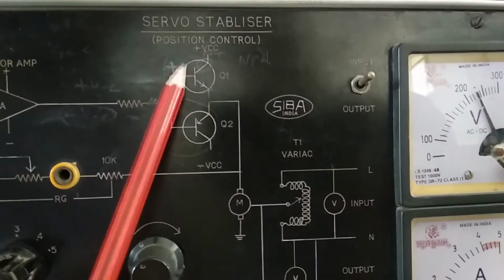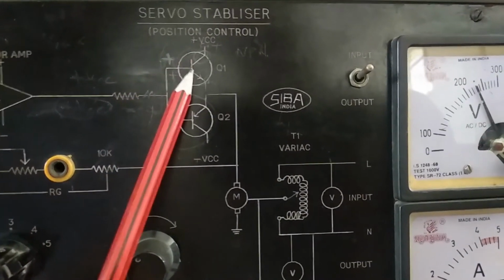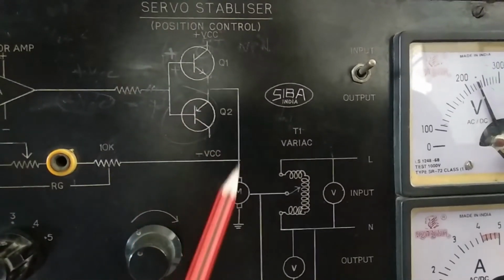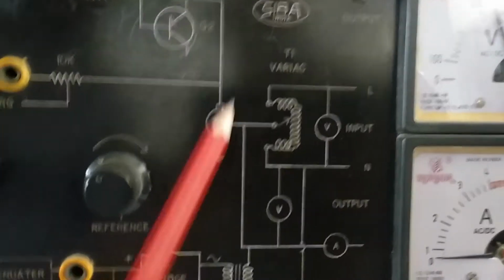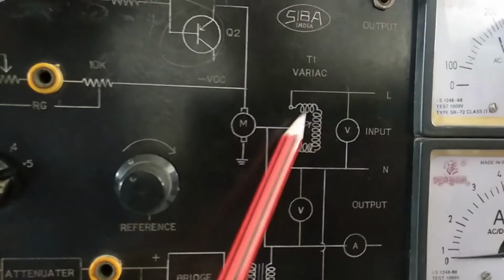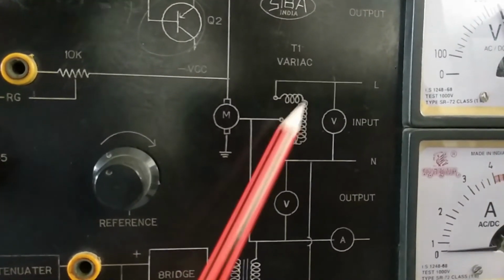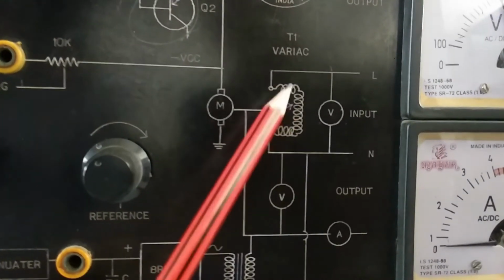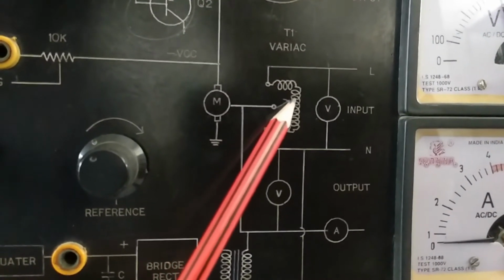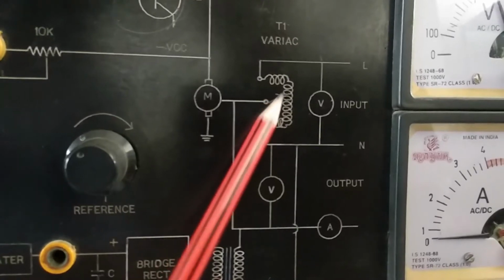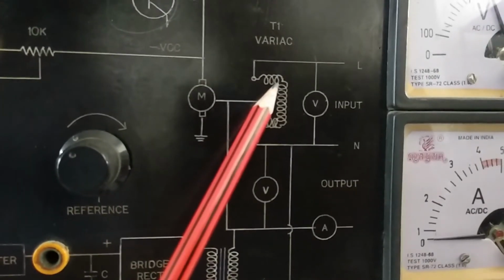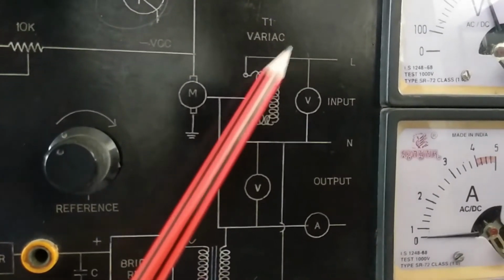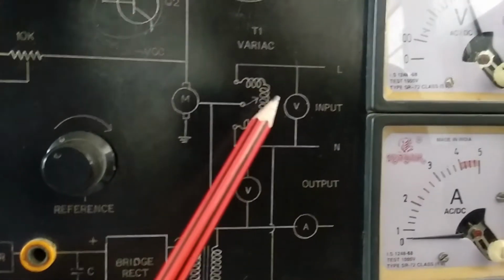This transistor conducts because of this signal, and it drives the servo motor. The servo motor is connected to the wiper of the transformer, which moves the wiper to the top portion of the winding to increase the voltage to 230 volts, applying the voltage correction.